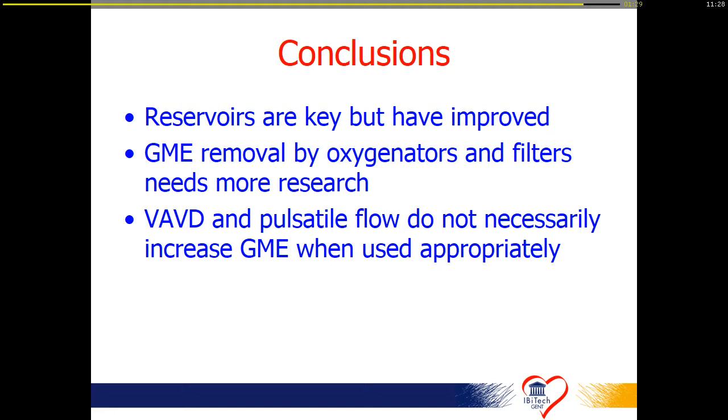I think that for years, the vulnerable part in the circuit was certainly the venous reservoir. I think everyone would agree on that. But I have to say the industry has taken the message, and now we have several companies who have markedly improved GME removal in their venous reservoirs. However, as long as we keep an open reservoir, based on its working principle, we will generate GME, that's for sure. And if you want to remove that, we have to rethink going to MiECC systems, going to other approaches. That's open for discussion, but then we have to go further than just looking at the different components.